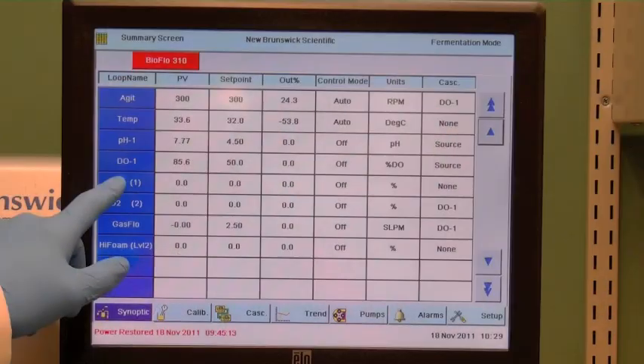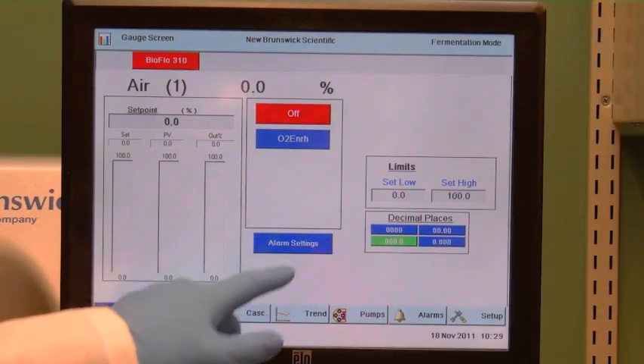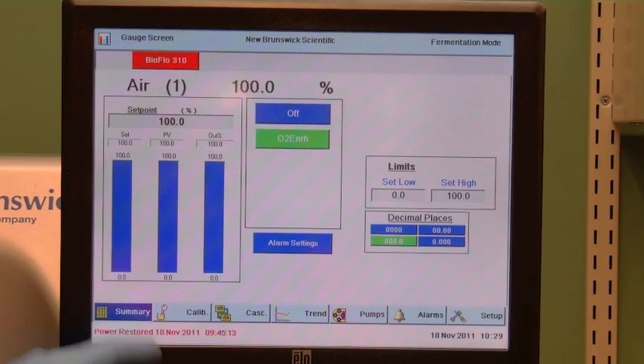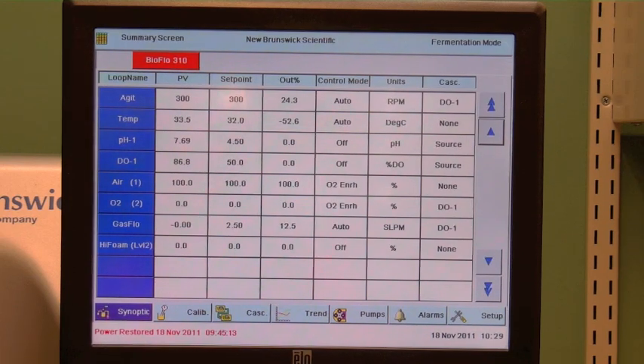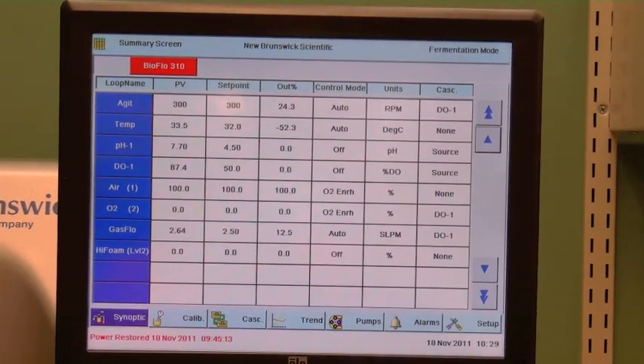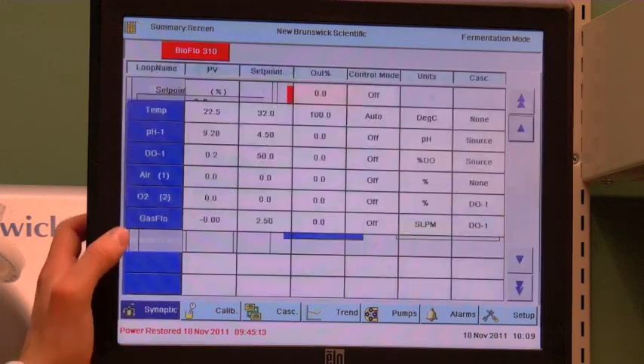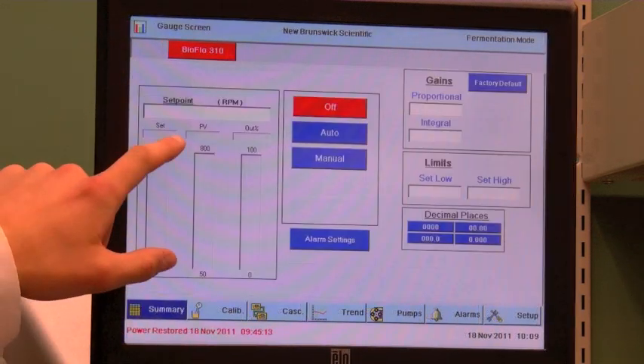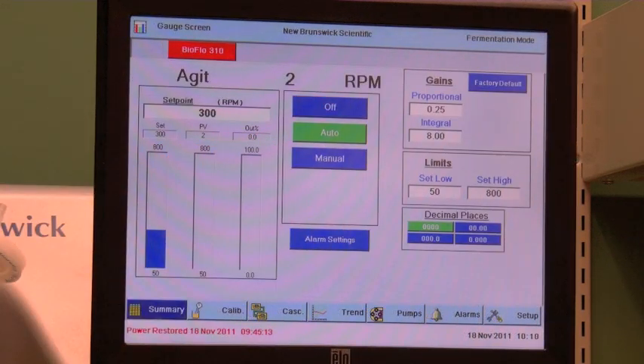Set the aeration rate by turning the red dial on the wall counterclockwise until gas flows, and selecting the O2 enrichment under the air tab. Set the agitation by changing the agitation control from off to auto and entering the fermentation speed of 300 RPM into set point.